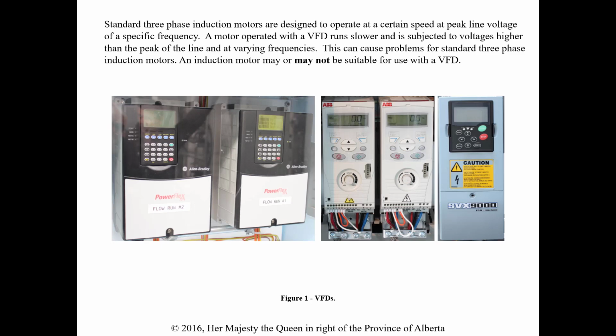Not all induction motors are going to be suitable, and it can actually burn up the windings, cause arcing at the bearings, and just basically make it so that the shaft won't turn. So basically render the motor useless. So we do have to be careful when we hook motors up to these VFDs that they're rated for such. The big thing again with the VFD, variable frequency drive: we're varying the frequency of the supply to the motor so that it operates slower or faster. And we can do that with the VFD.